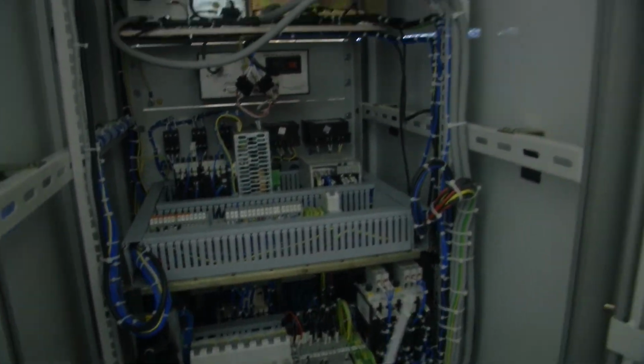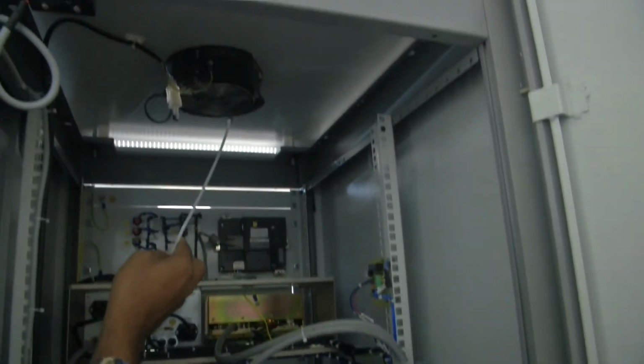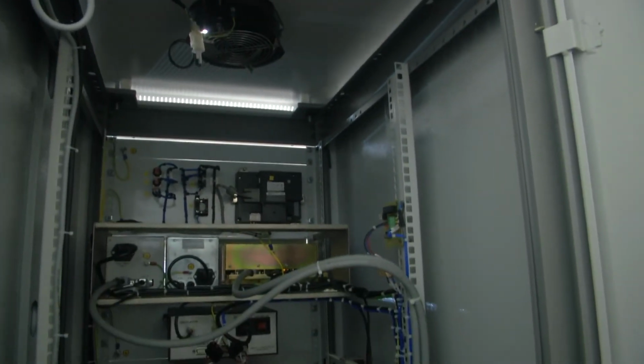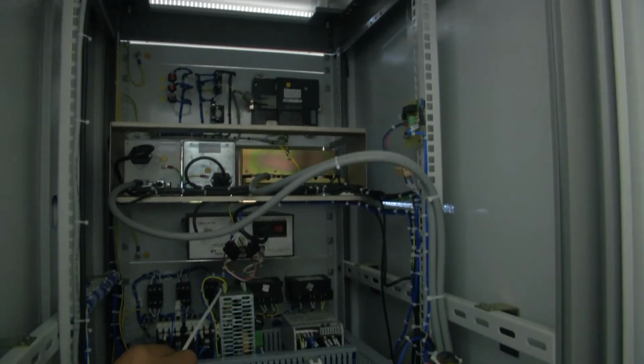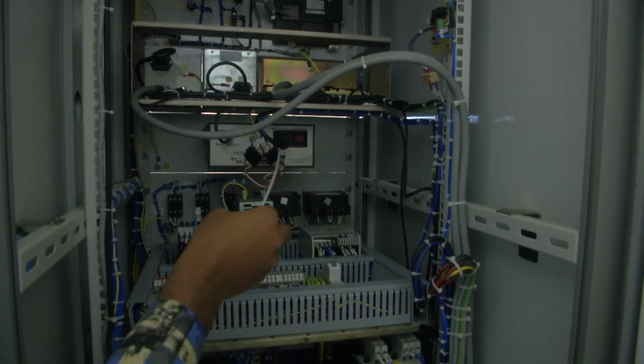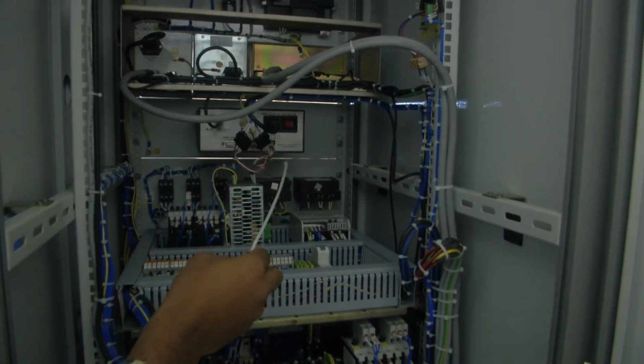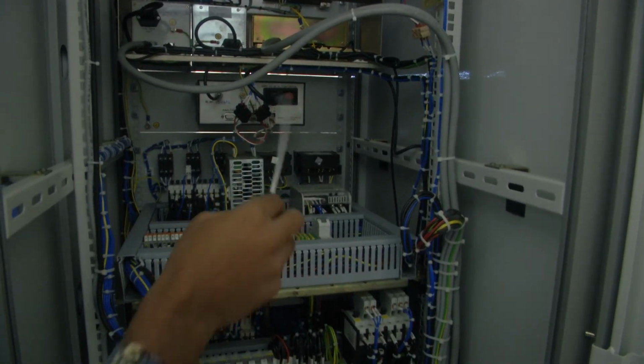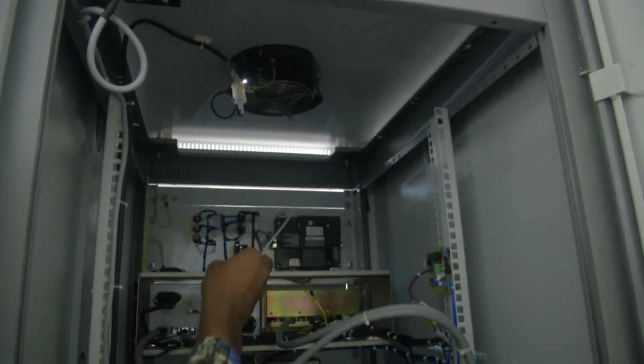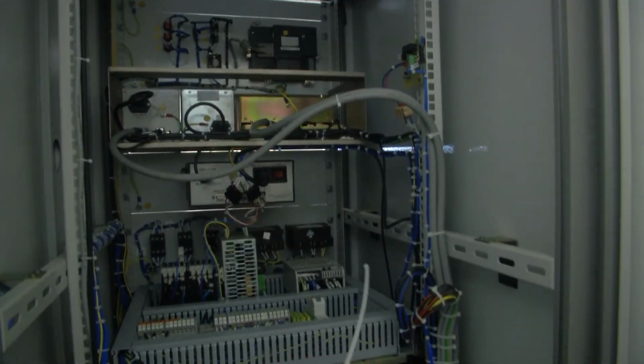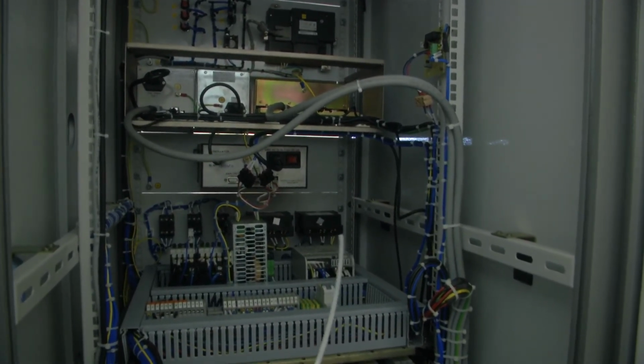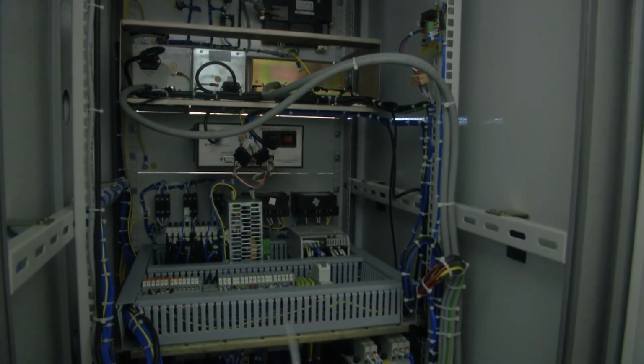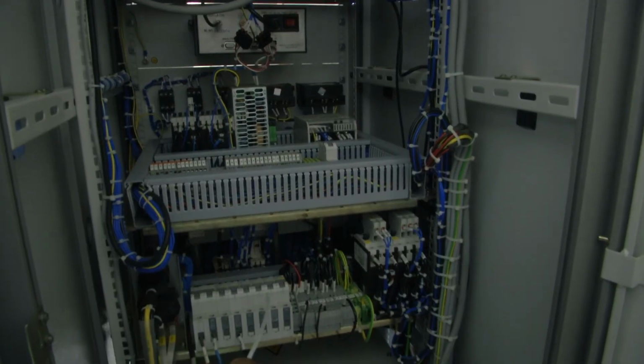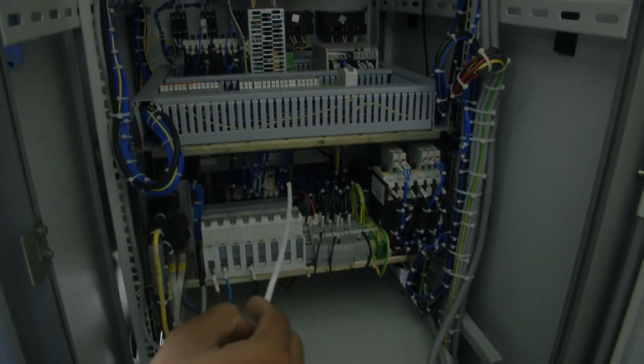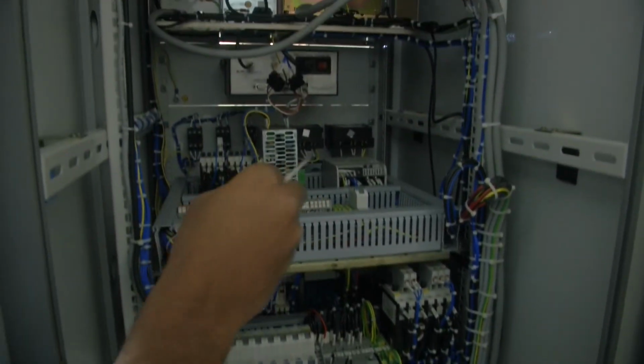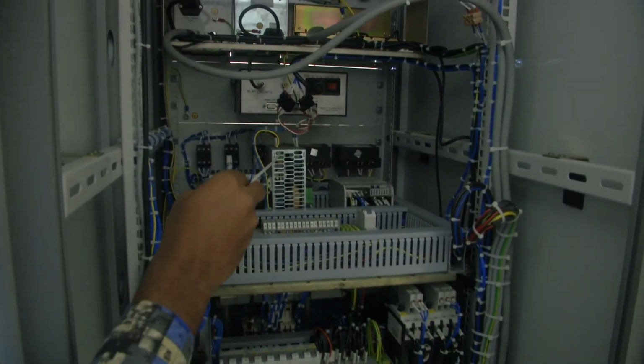See, when we turn on the system, initially this fan will get on to cool all the accessories like the thyristor. We give a 24 DC power supply for control circuit purposes. The DTM is also inside, and the transformer is there. For cooling all the accessories we give a fan, and the HMI is also there. Sometimes if some selector switches do not turn on, we have to troubleshoot. At that time we have to observe the MCBs also, in case some MCBs are tripped. And this is called a contactor, and thyristor, 24 DC supply. This is for the control circuit.